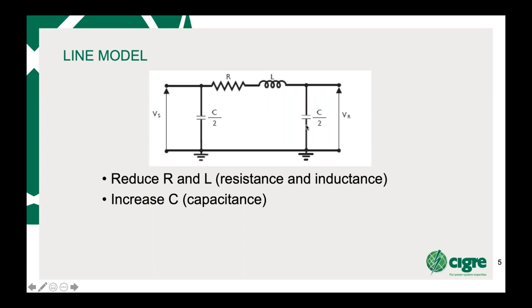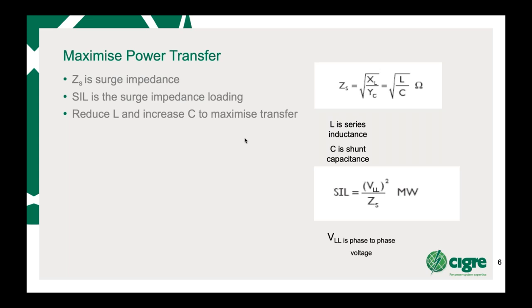Let's have a look at how we then maximize the power transfer. What they look at is a thing called a surge impedance, and the surge impedance loading, SIL, is given by this formula down here: V_LL, the line-to-line voltage, over Z_S, and Z_S is root L over C. So really what you want to try and do is reduce this, so increase C, reduce L. L is the series inductance, and C is the shunt capacitance. So you reduce L and increase C to maximize transfer.